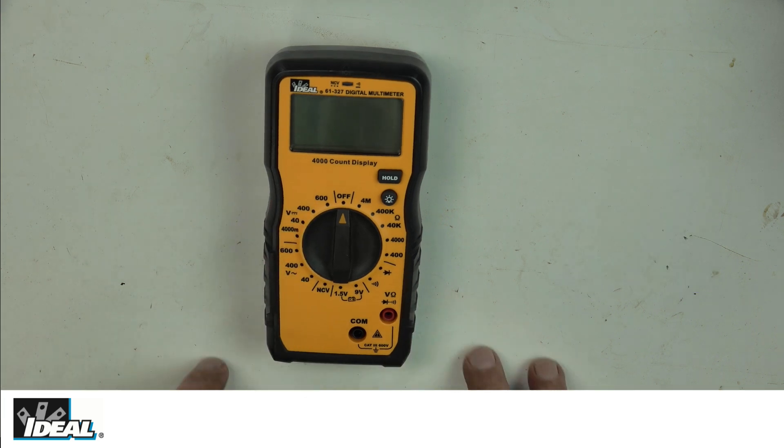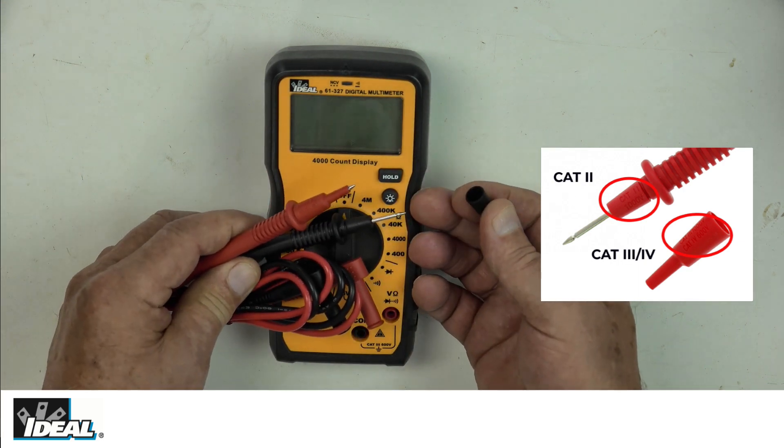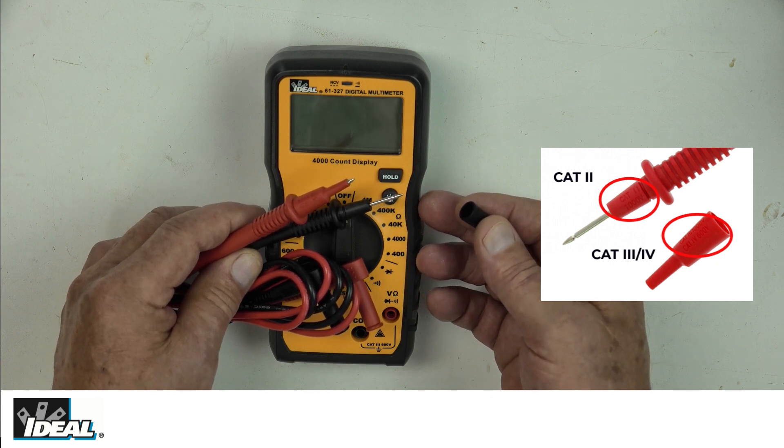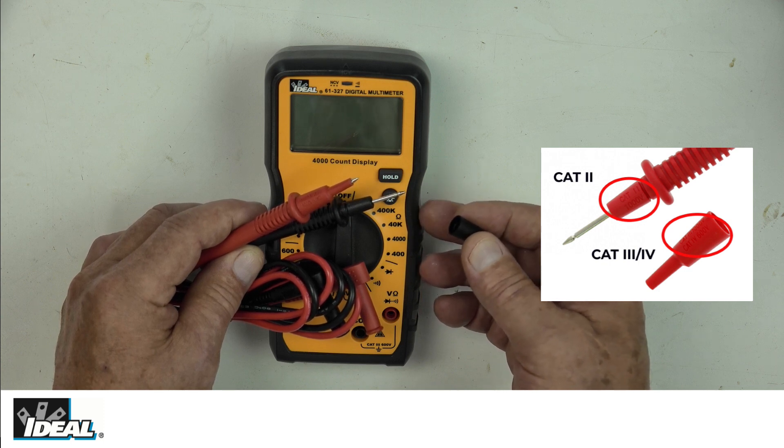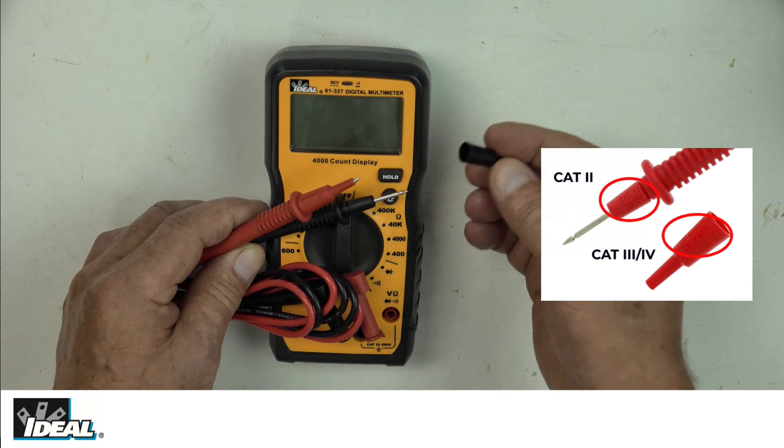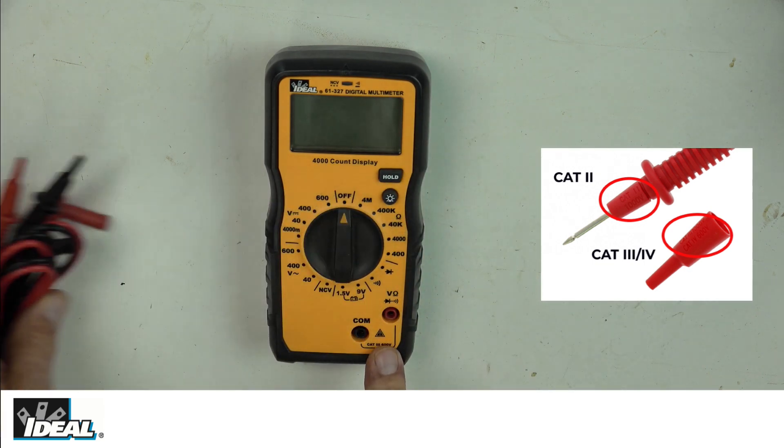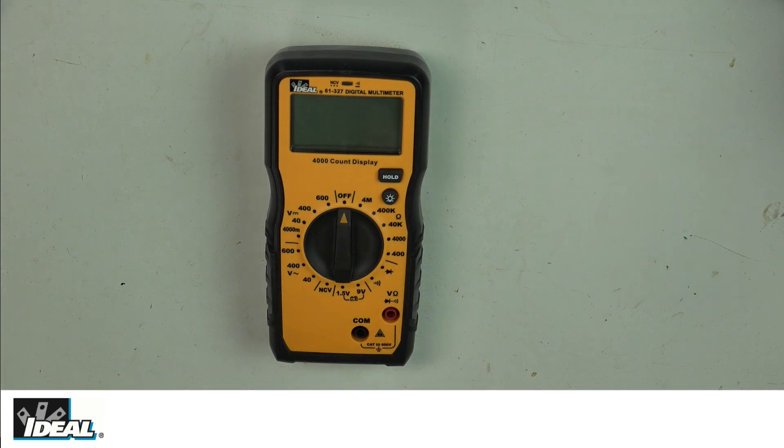The test leads that come with the tester have removable caps. If I'm using the tester in a Cat 2 testing environment, say at an outlet in a room, it's okay to remove them. But always hang on to these caps and replace them because if you use the tester in a Cat 3 testing environment, say at an electrical panel, you would need those protective caps.